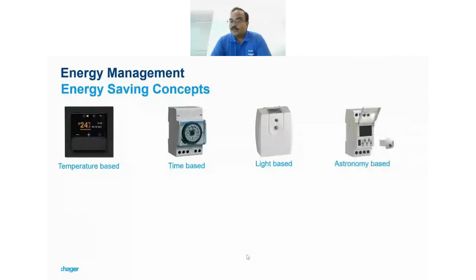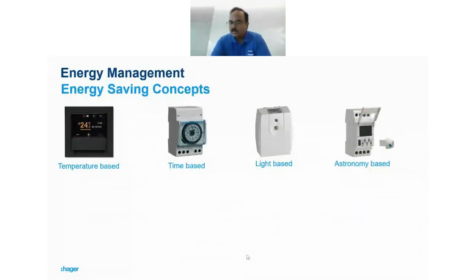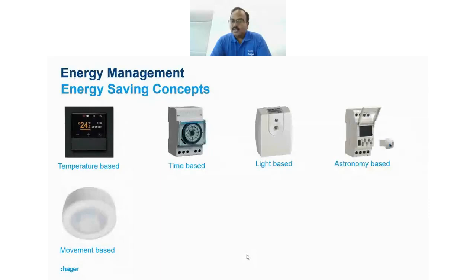There is even an astronomy-based concept where, depending on location, street lights can be controlled. A normal time-based switch doesn't account for seasonal variation — in summer there is enough sunlight until 7 PM, so why switch on street lamps at 6? An astronomy-based controller knows the location and automatically calculates sunrise and sunset times.